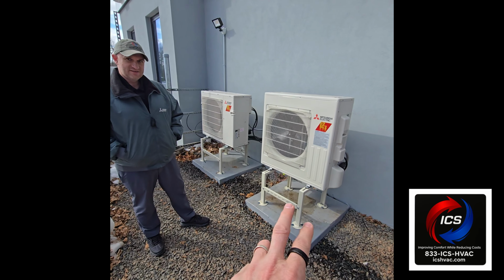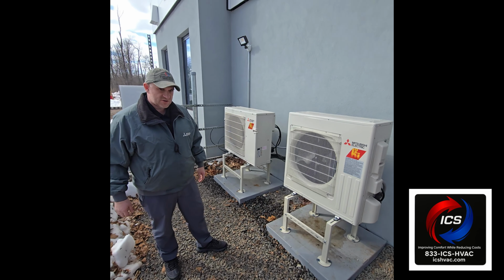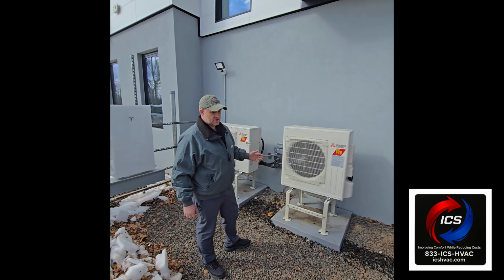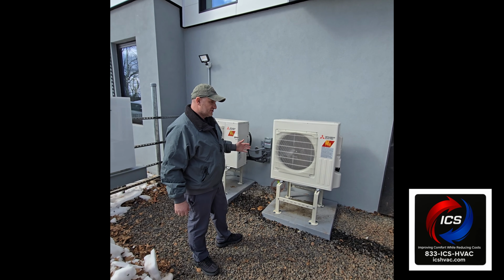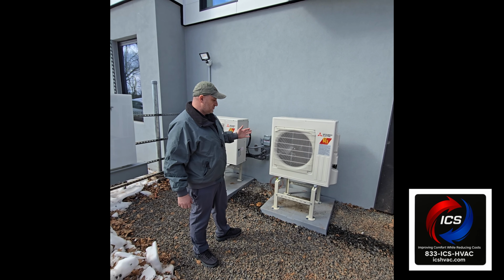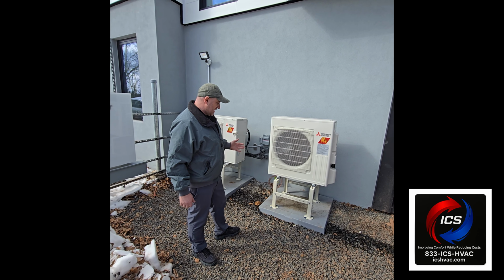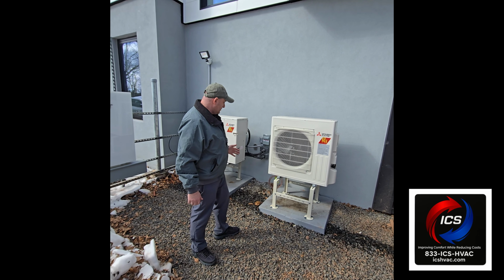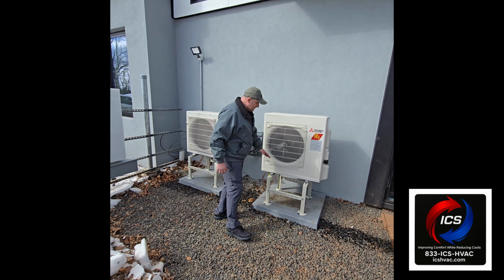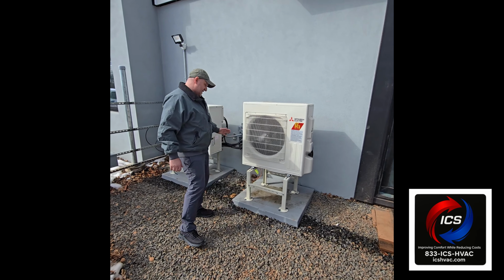Explain to me, why are these units raised? So these are hyperheat units. They may be relied on during the winter for the primary heating for the home, so we want to raise them to account for snow buildup. We do not want the snow blocking the fan, blocking the electronics, and damaging the equipment.